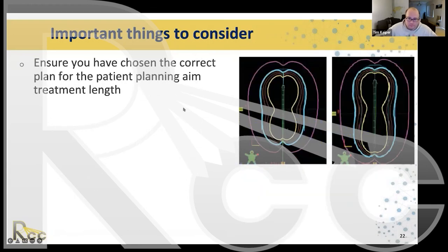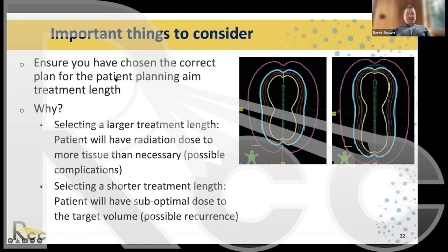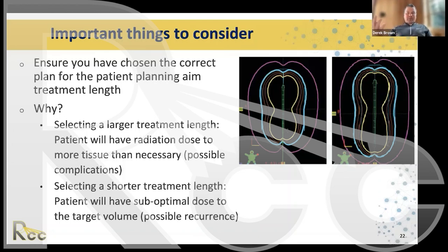Just as with cylinder diameter, we must ensure the planning aim treatment length matches the desired length. Selecting a shorter treatment length results in suboptimal dose to the patient; selecting a longer treatment length causes overdose. This is equally as important as selecting the correct cylinder diameter.